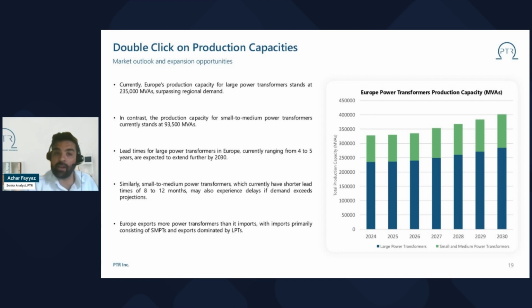Despite these capacity figures, lead times continue to be a challenge in European markets. Large power transformers currently have lead times of 4 to 5 years, and with demand expected to outpace new capacity addition, these delays may increase further by the end of the decade. For small to medium power transformers, lead times are shorter, typically 8 to 12 months, but even here sustained demand growth could introduce delays if capacity isn't scaled proportionally.